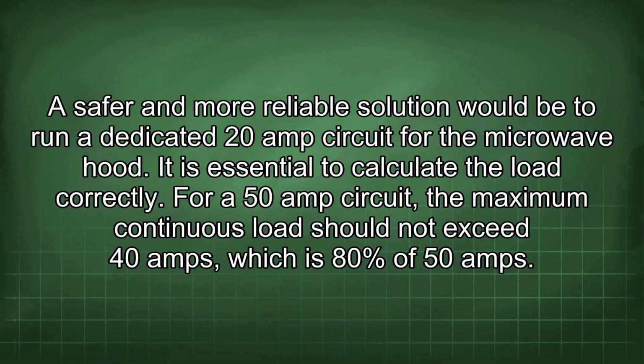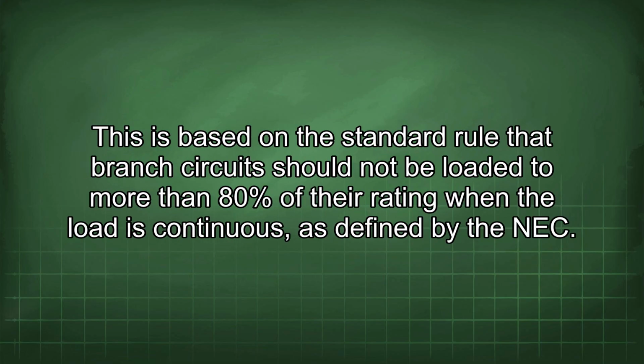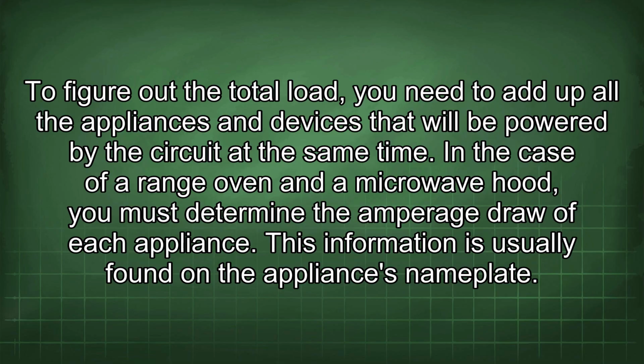It is essential to calculate the load correctly. For a 50 amp circuit, the maximum continuous load should not exceed 40 amps, which is 80% of 50 amps. This is based on the standard rule that branch circuits should not be loaded to more than 80% of their rating when the load is continuous, as defined by the NEC. To figure out the total load, you need to add up all the appliances and devices that will be powered by the circuit at the same time. In the case of a range oven and a microwave hood, you must determine the amperage draw of each appliance. This information is usually found on the appliance's nameplate.